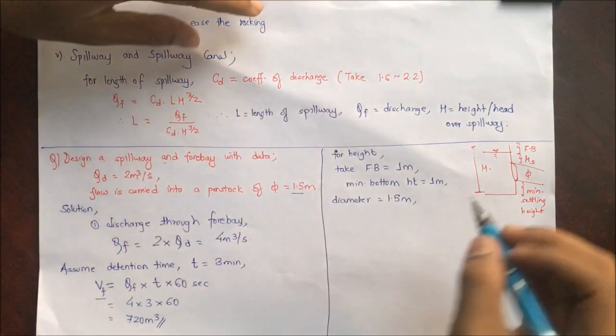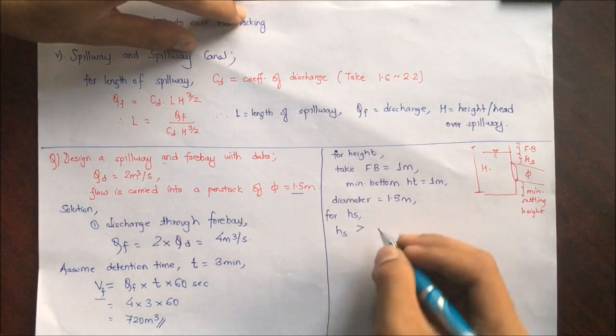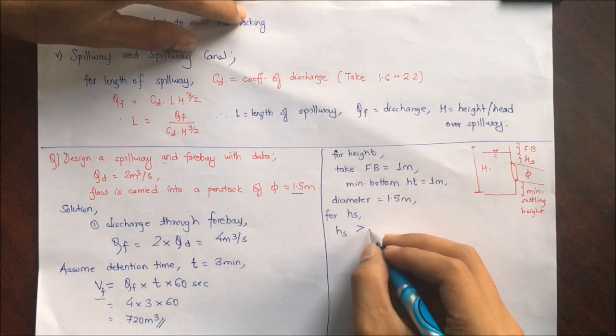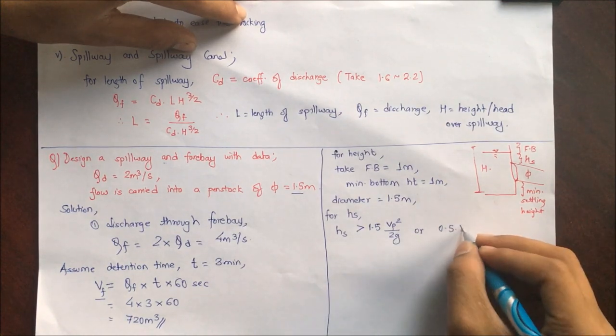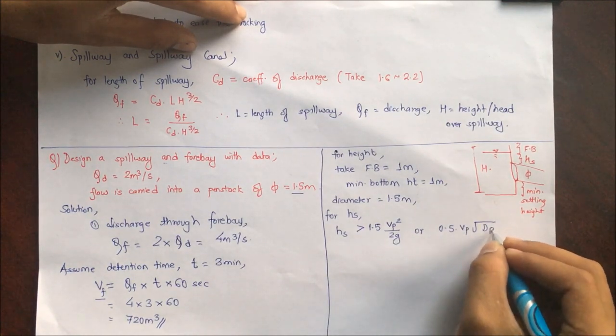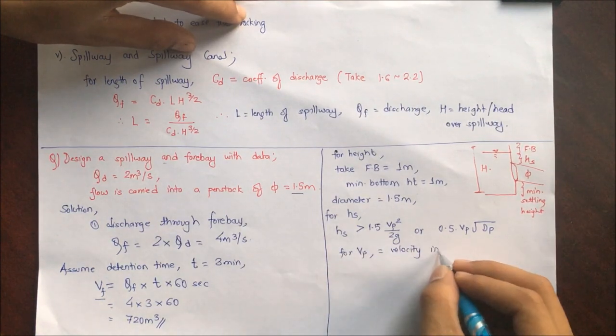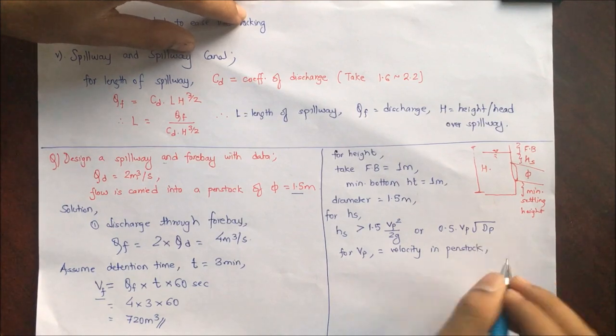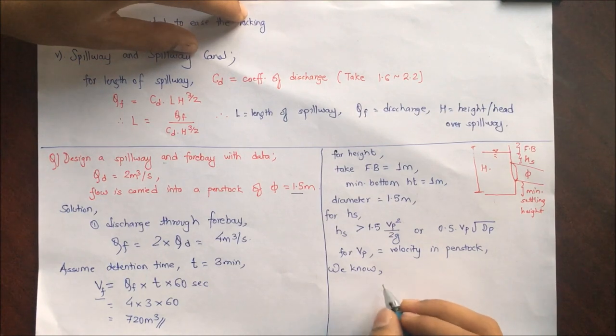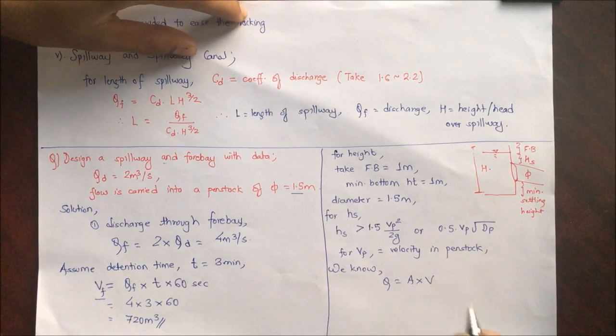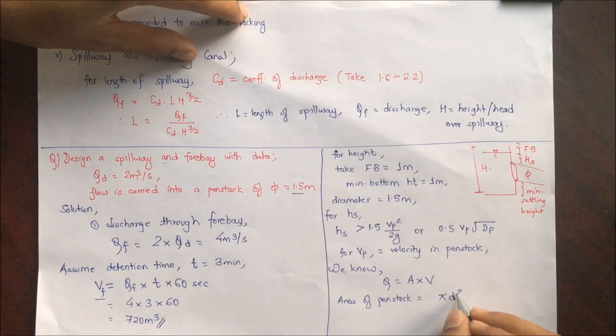For submergence height Hs, we have two conditions: Hs > 1.5 × Vp² / 2g, or Hs > 0.5 × Vp × √Dp, where Vp is velocity in penstock. To find Vp, we use discharge Q = A × V, where area of penstock Ap = π D² / 4, with D being the diameter of penstock equal to 1.5 meter.